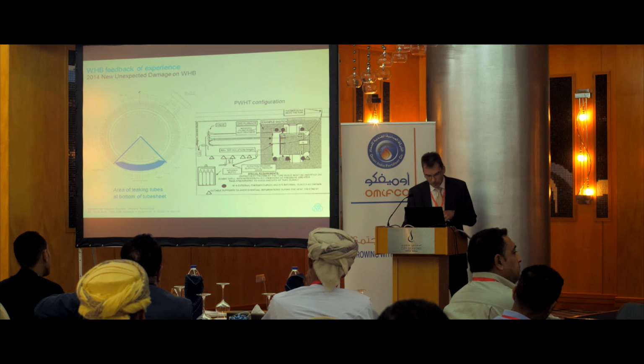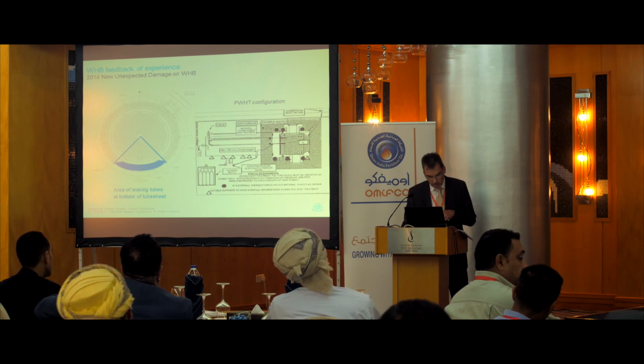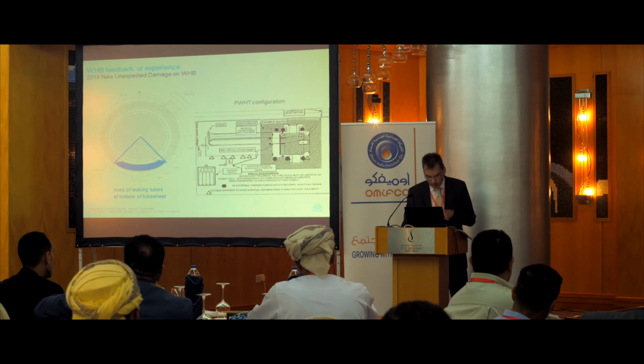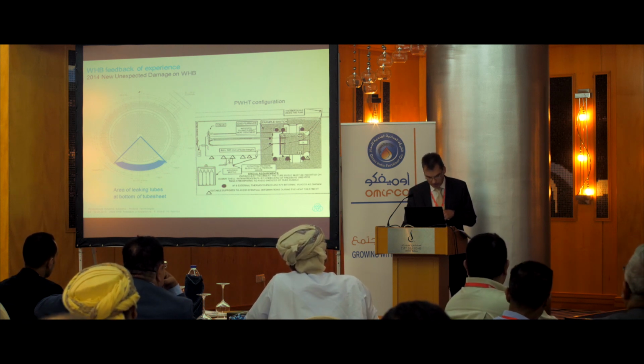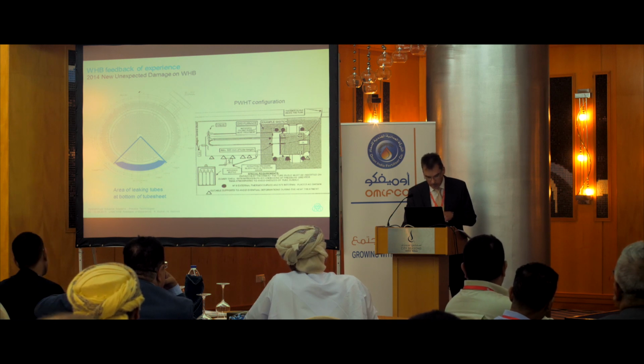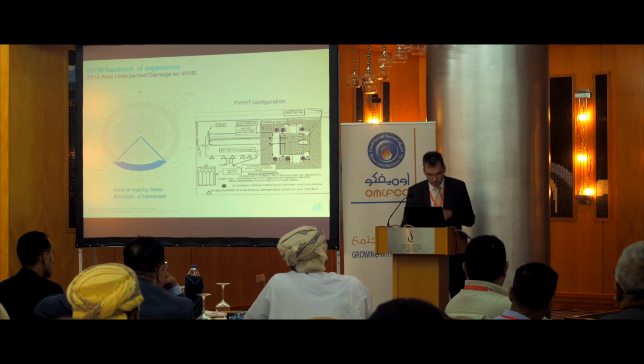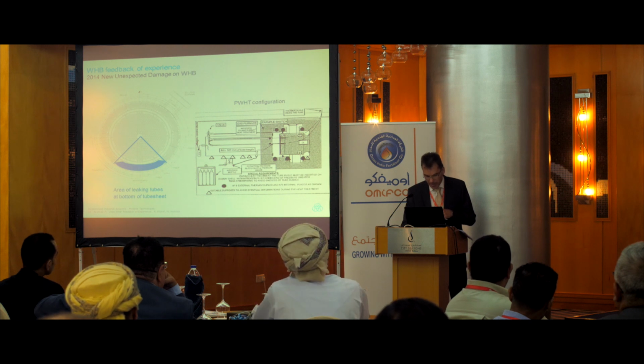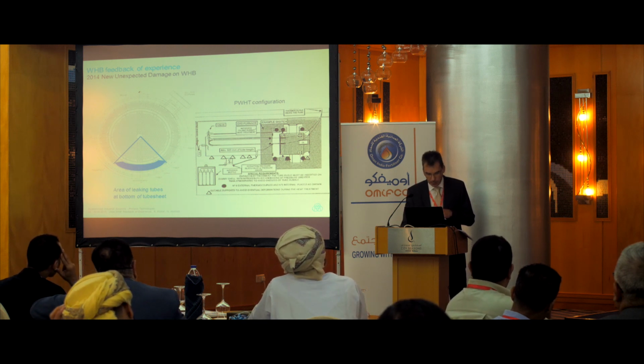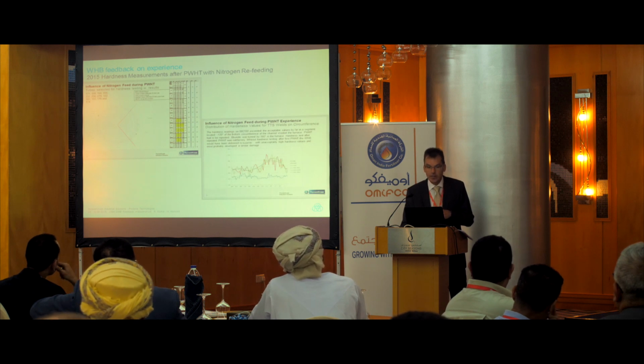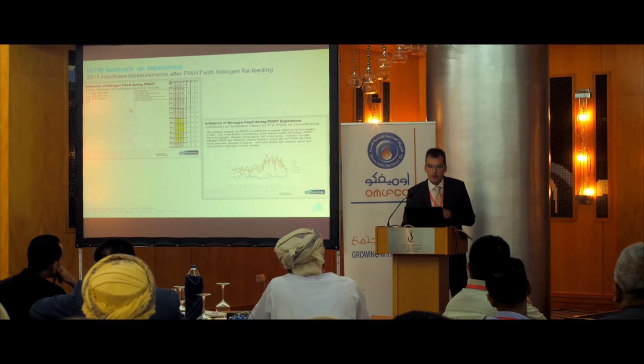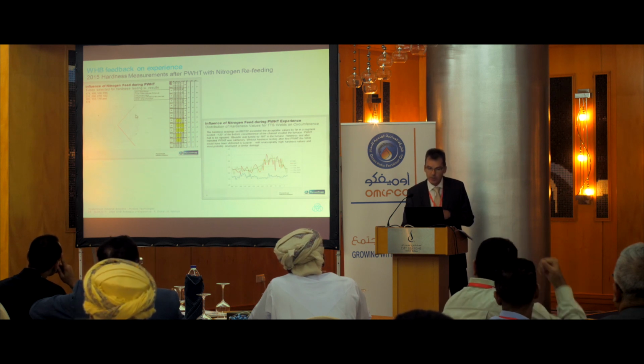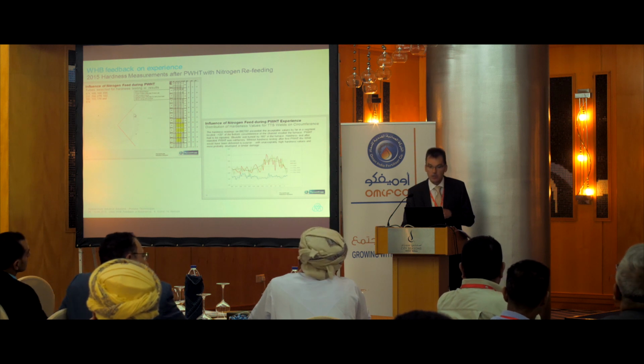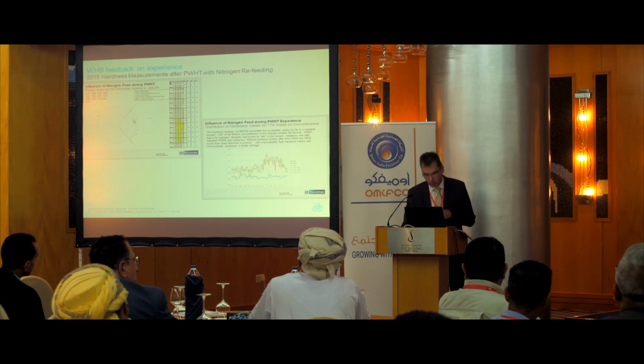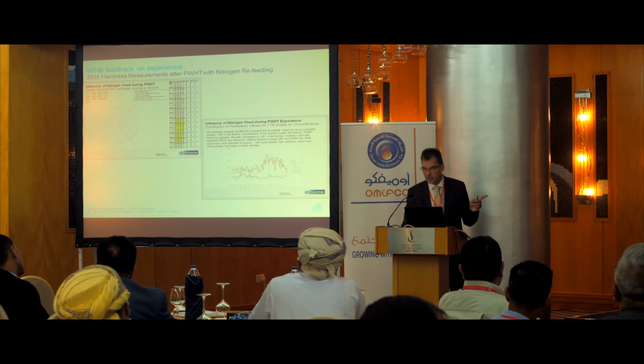But more, during the fabrication of new boilers in the plant in the USA, again during post-weld heat treatment, cracks had been noted on the seal weld. And again nitrogen was fed in. But this time we had the chance to check the fabrication and do hardness measurements on selected tubes. The results proved that in sectors of about 120 degrees, which you see here, which is again, if you turn it down, the location where the waste heat boiler was heat treated, we have very high hardness values, which of course proves that this is the reason that the cracks occurred in the other waste heat boiler during operation.